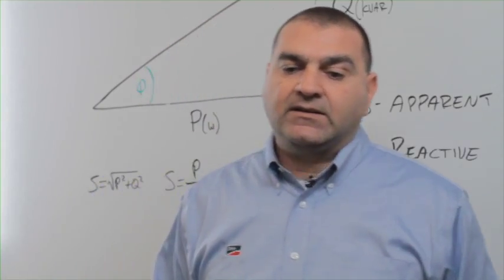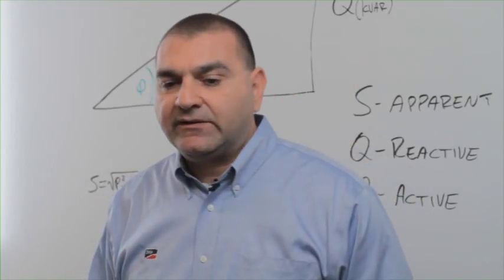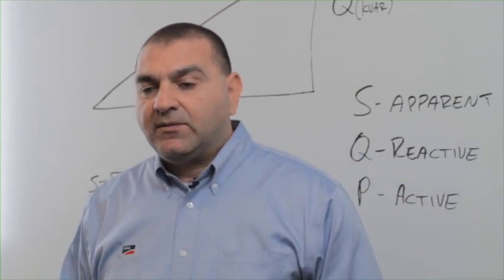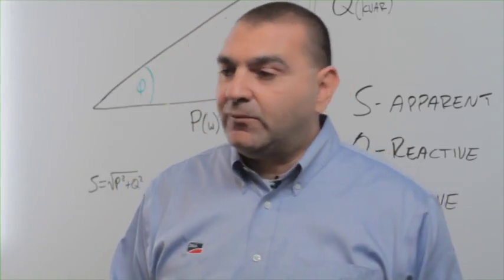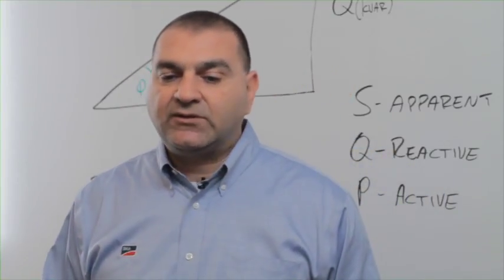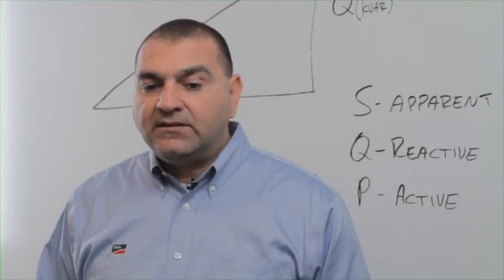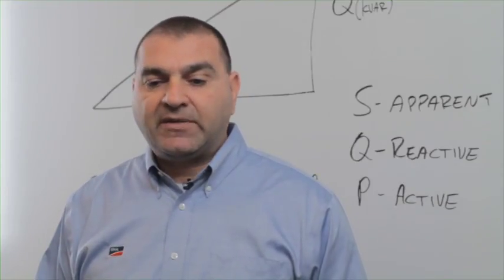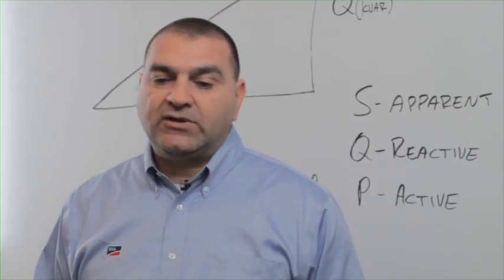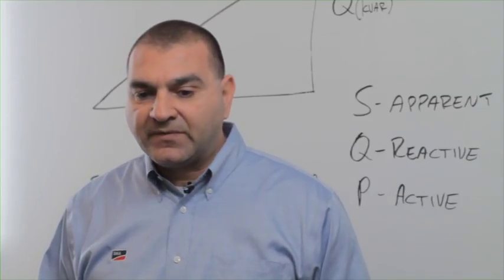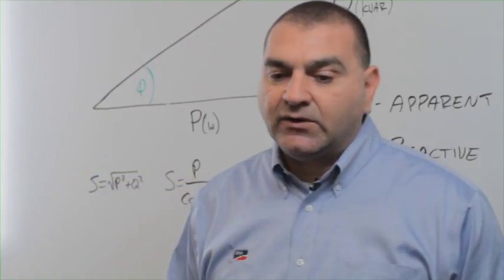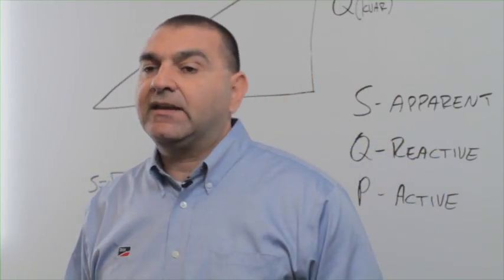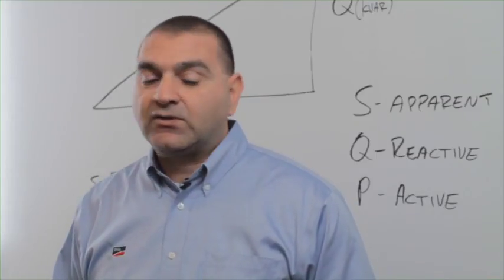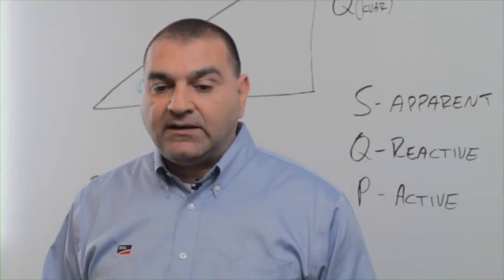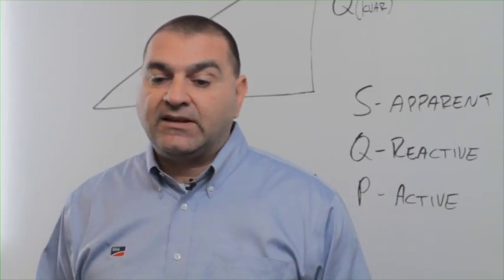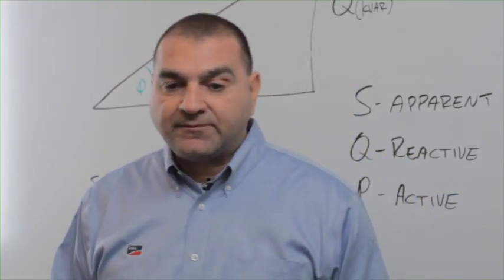So currently, the PV market is regulated by IEEE 1547 and UL 1741, but this business is being transformed from what we used to call PV business into becoming now an energy business. And PV power plants now are contributing and becoming generation assets to utilities and conventional power producers. So utilities, ISOs, and reliability coordinators, unfortunately, are still applying the conventional large generation interconnection applications to PV power plants, and that's because of the lack of information and lack of standards for the PV interconnection.